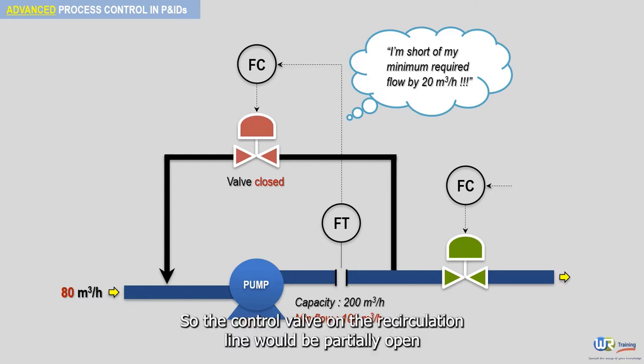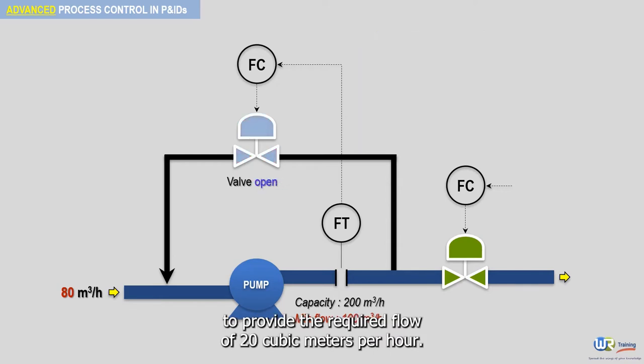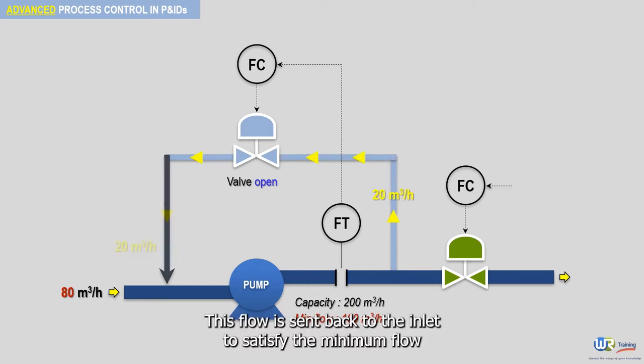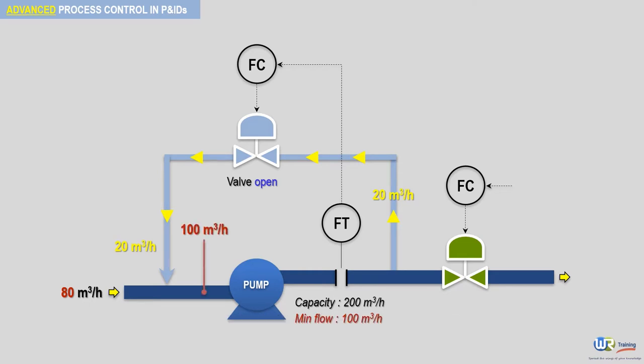So the control valve on the recirculation line would be partially open to provide the required flow of 20 cubic meters per hour. This flow is sent back to the inlet to satisfy the minimum flow condition of 100 cubic meters per hour and thus prevent damage to the pump.